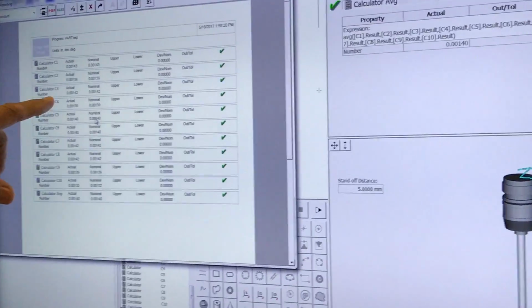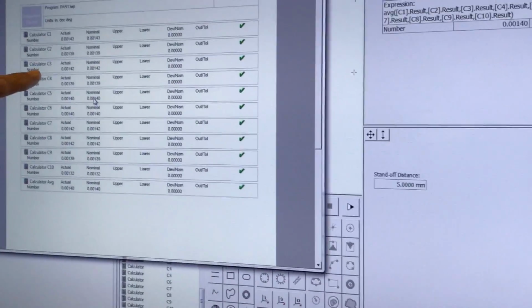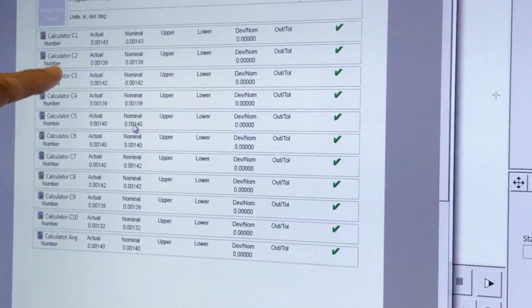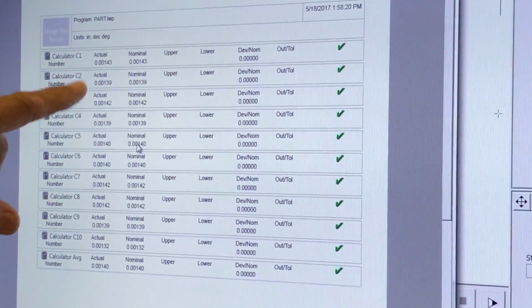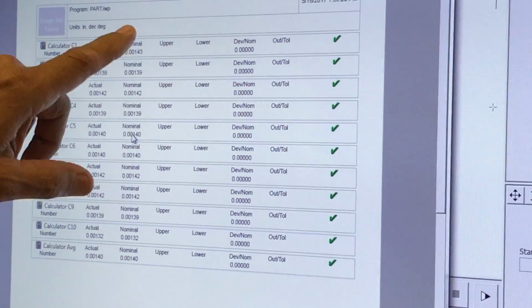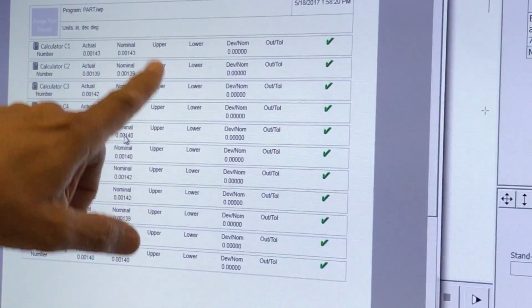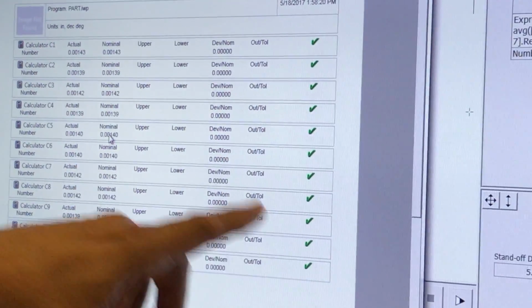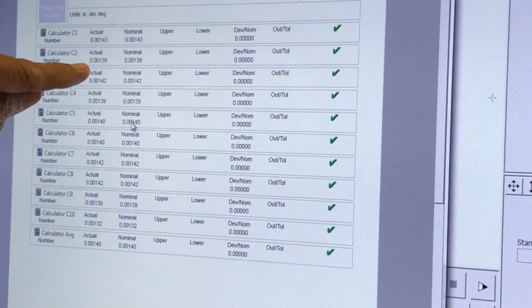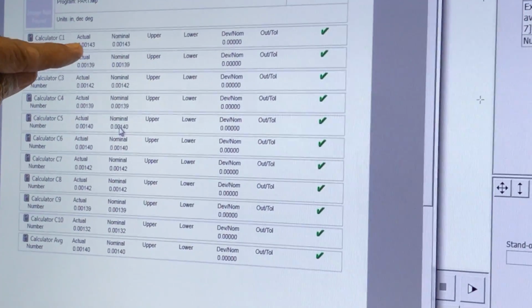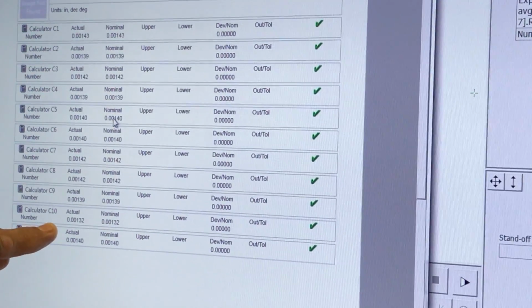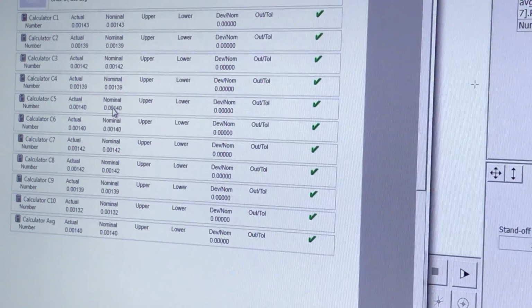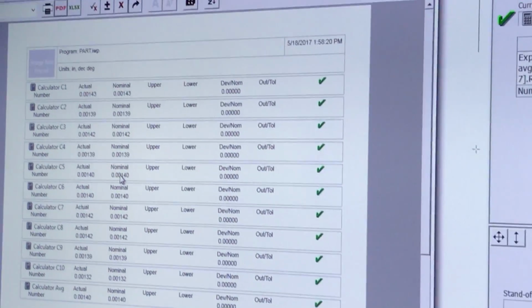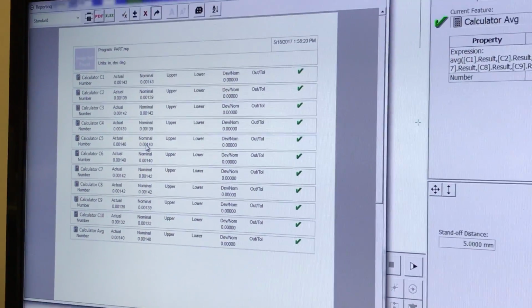this case, the difference between the thickness with the coating and without the coating, giving me what the thickness of the coating is. It gives me the actual values, the nominal values, and we can also put an upper and lower spec limit that tells me what percentage out of tolerance is. The main thing, though, is that we've got the coating thickness in all 10 locations, and this information can be sent straight to an Excel spreadsheet, or it can be presented in a report like this. This concludes this demo.